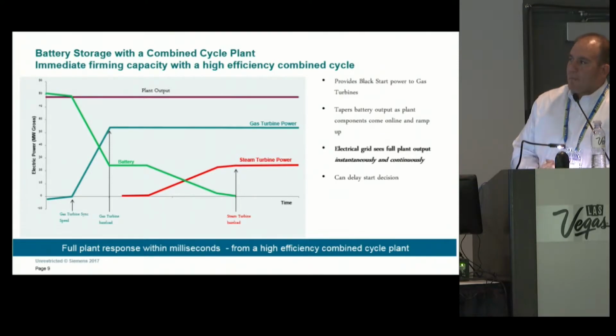Gas turbines ramp up while the battery ramps down to maintain that constant output. Then it holds, and while the steam turbine warms up, the battery holds and then ramps back down as the steam turbine ramps up.